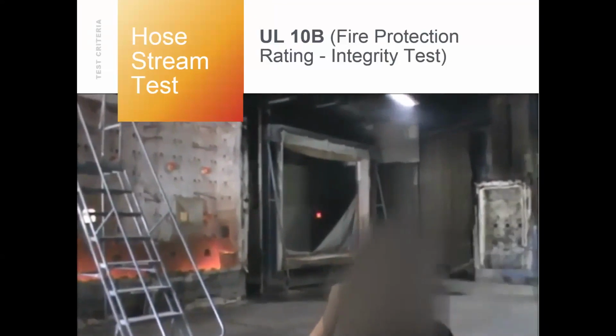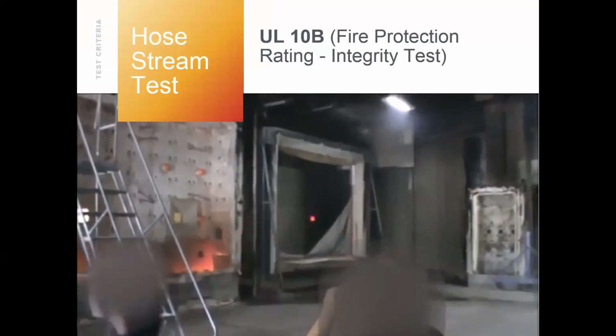Did it pass? Did not pass. So that's kind of a brutal summation of what we're talking about here. Fabric product under UL 10B can never be placed in structural openings, because it fails that test every single time. And that's not this manufacturer, that's every manufacturer.